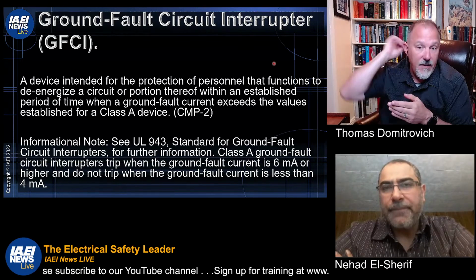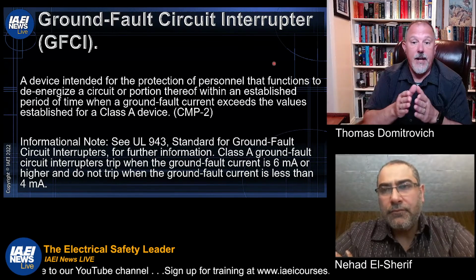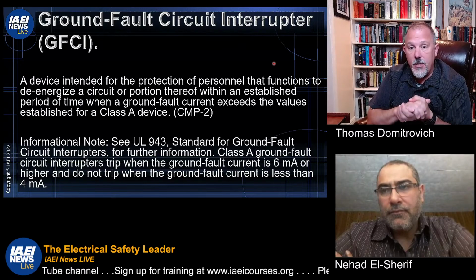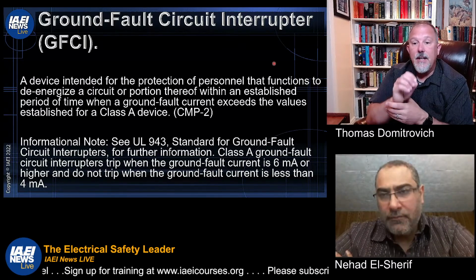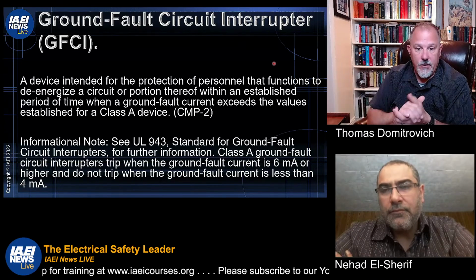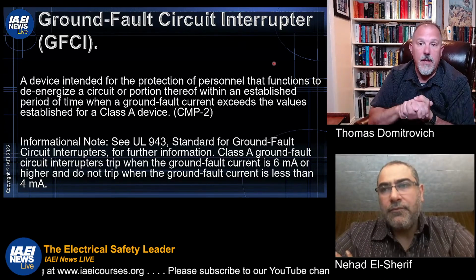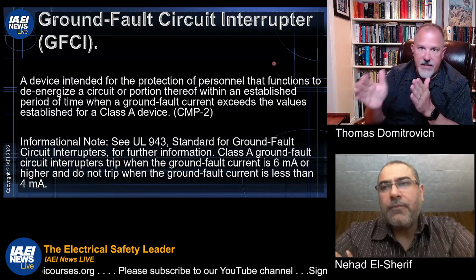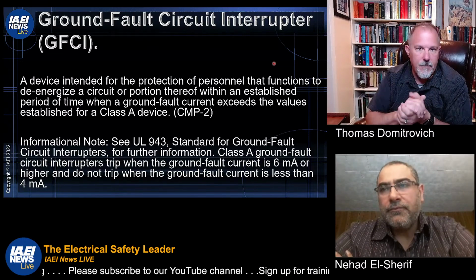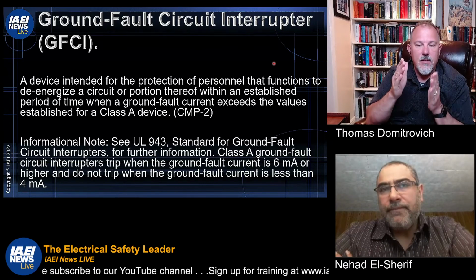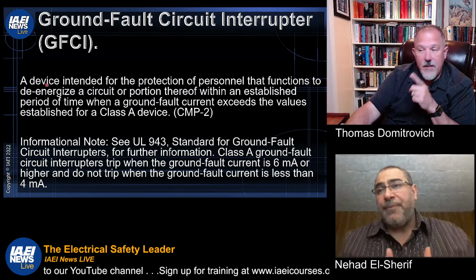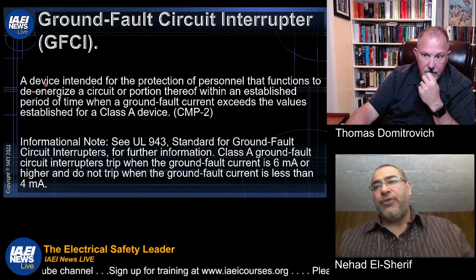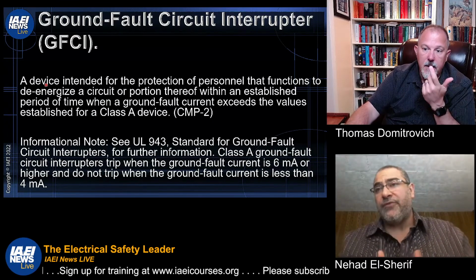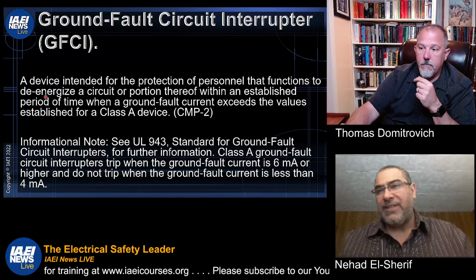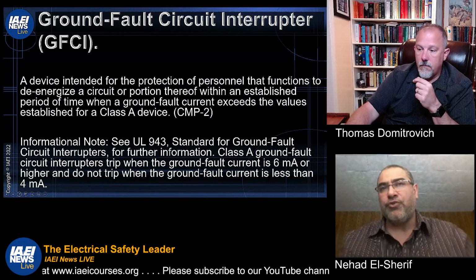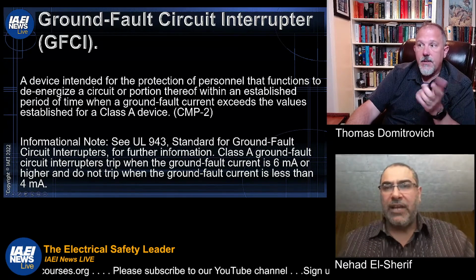UL 943 is the standard, and it says a Class A ground fault circuit interrupter trips when the ground fault current is 6 milliamps or higher and does not trip when the ground fault current is less than 4 milliamps. That's why a lot of people say a 4 to 6 milliamp device or a 6 milliamp device. Some people refer to Class A as 5 milliamps plus or minus 1. It's all the same: you trip when it's 6 or higher, and you don't trip when it's 4 or less. Okay, so that's your GFCI.